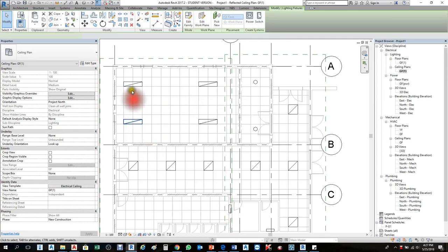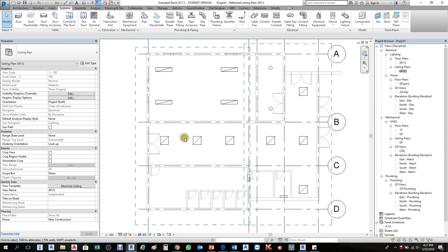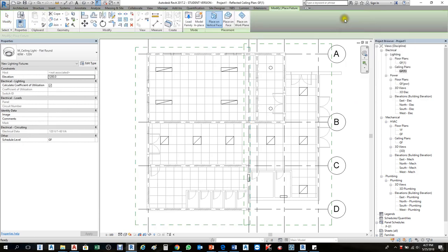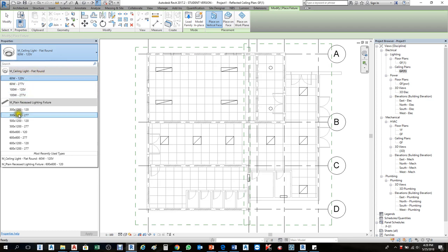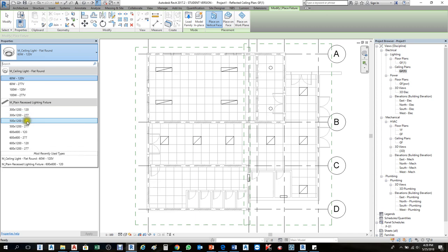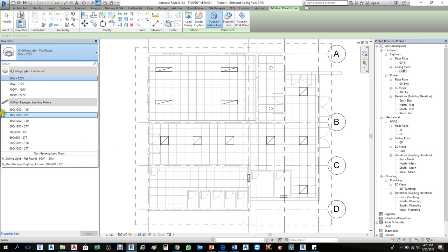I created three types of lighting fixtures here. To create a lighting fixture, go to System then Lighting Fixture. Once you click Lighting Fixture, the properties palette gives you choices. You have ceiling light types, recessed fluorescent types, and more. Be careful about voltage — it shows the voltage and ampere here. For example, 120 or 277. If you choose 120, every light fixture gets the same 120 voltage.